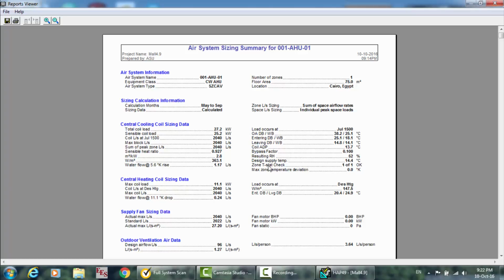This will tell you whether you want it drier or you accept this result, so it's up to you. And here the design supply temperature, this is the theoretical supply temperature, it's 14.4, but according to the calculations the supply temperature will be 14.8. It is a psychrometric issue related to the psychrometric process. You have to know that not all you want will you get. You will get what it is according to the calculations.